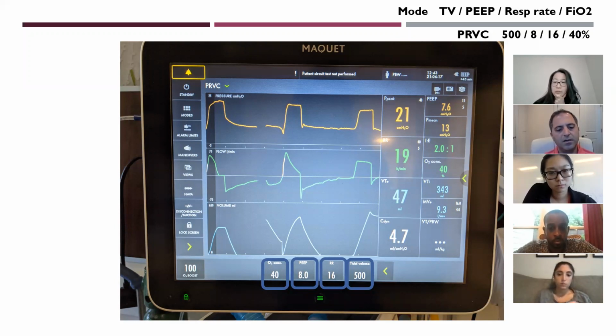No. So these Servo-U Maquet machines are only, I think, 10 years old. As Nancy mentioned, the reason that we're not putting everyone on PRVC is we just don't have the technology in all these ventilators. Believe it or not, some of our ventilators are 20, 30 years old. So some of them just don't have the brains for it. The machine needs to be fast enough to make decisions, sophisticated enough to measure flow and pressure at very short intervals, literally milliseconds, during the delivery of the breath, to decide what to do with the flow and pressure.